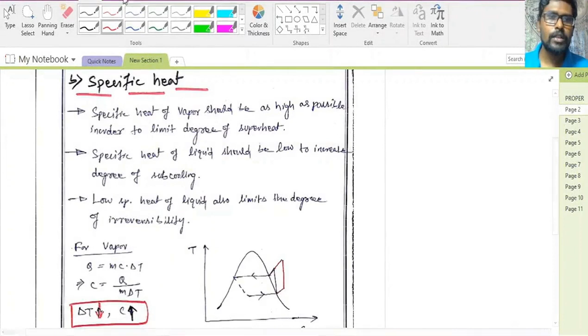Now the second thermodynamic property is the specific heat. In our refrigeration cycle, the refrigerant changes phase from liquid to vapor and from vapor to liquid. In the vapor state, the specific heat should be high. If the specific heat of the vapor is very high, the degree of superheat will be low. In the liquid state, the specific heat should be low, so we can increase the degree of subcooling.